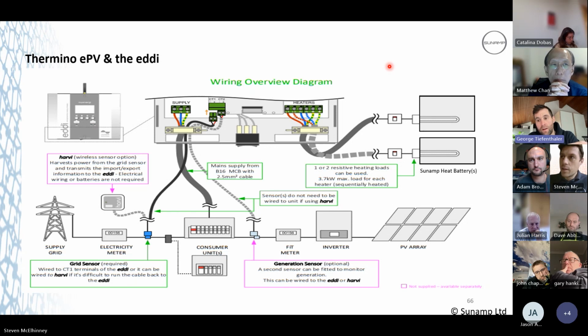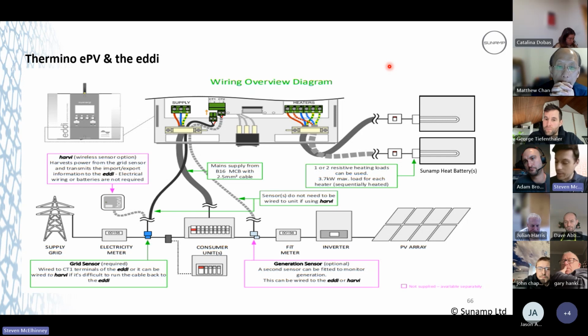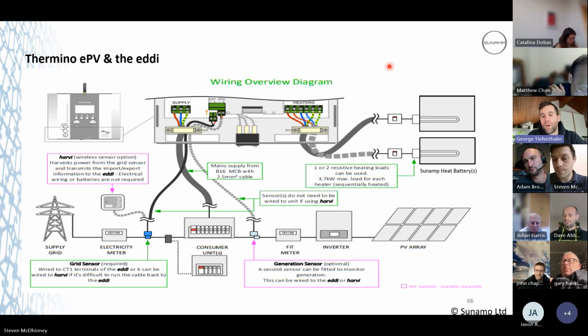Would that be right? It's all depending on your incoming supply as well, George. So you do get a pressure drop across the heat exchanger, which is in our manual on a chart, so at the end of this we can quickly bring it up to show you. For 15 litres per minute, it's something like 0.2 of a bar pressure drop. So you'd have 0.4 if you're designing that system with the 2 batteries.